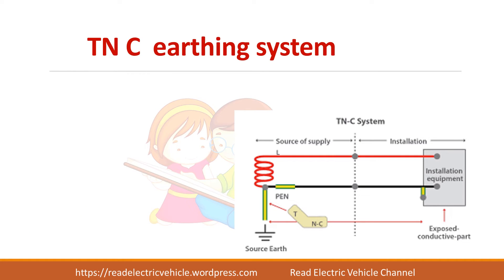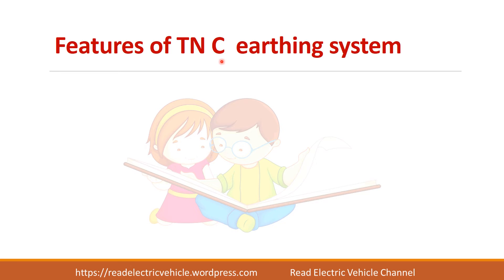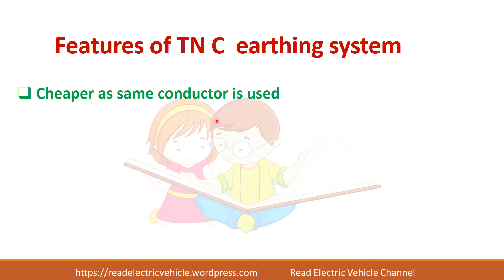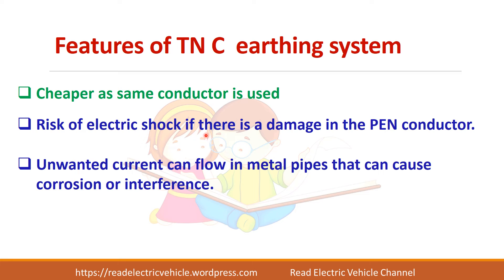The next type is the TNC earthing system. C stands for combined, so the neutral and protective functions are combined in a single conductor — called the protective earth neutral (PEN). The source side is T, directly connected; the second letter indicates neutral; and the third letter C means two conductors are combined into a single one. TNC is cheaper than TNS because only a single conductor is used. However, if this conductor breaks or is damaged, you will get a shock, so this type of system is normally not preferred.